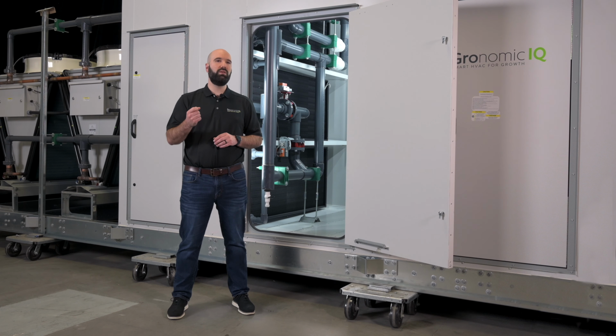That second pump that was in the return air section is to create that second chilled water loop, and it's a loop that is entirely separate from the compressor heat rejection loop, or I guess the heat rejection loop bleeds into that loop, in order to have a cold loop and a hot loop. And we'll talk about the hot loop again one section further on. But that allows us, again, with our internal controls, to control the chilled water function or the Economizer function and the heat rejection function in a simultaneous way. All of the controls for this are internal. There's nothing that you need to do as a customer or as an installing contractor to get this to work. It's built in, it gets put on site, and it works. Again, our real goal there is to make the integration of this equipment, the startup of this equipment, as easy and as seamless as possible.